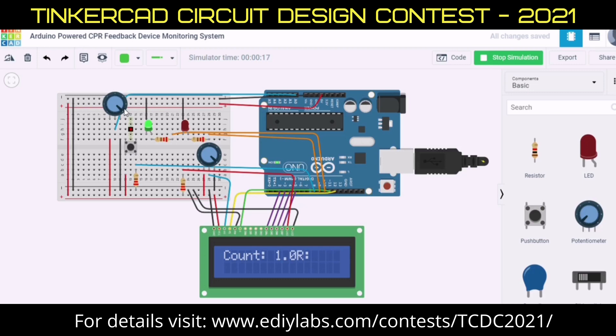We have to reduce the pressure — and it will automatically turn the red light on. Here you can see the red light is on, indicating to the patient that insufficient pressure is being applied.